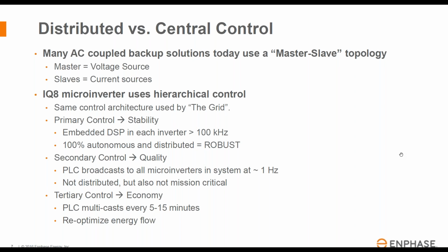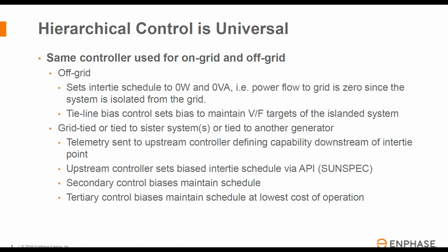Next slide. So the hierarchical control is universal. We're using the exact same controller, whether it's for on-grid or off-grid. And the primary difference there is in off-grid, what we do is we set essentially an intertie schedule. And that's basically at the control point where you would typically intertie to the grid. We put an isolation device. We would isolate from the grid.